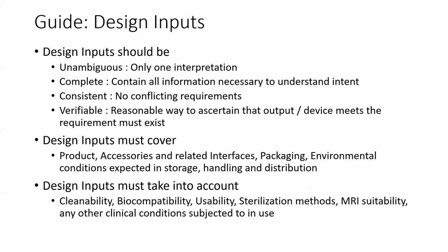most startup ideas, and most startups who come up with something novel, who have an idea, don't really look at or bother to document in a manner in which it is eventually required to assure design control and design safety eventually. So one of the important aspects of documentation is writing design inputs. And the benefit of writing comprehensive design inputs is the risk of missing design requirements during the design process is minimized. Okay, it saves you from your oops moment.